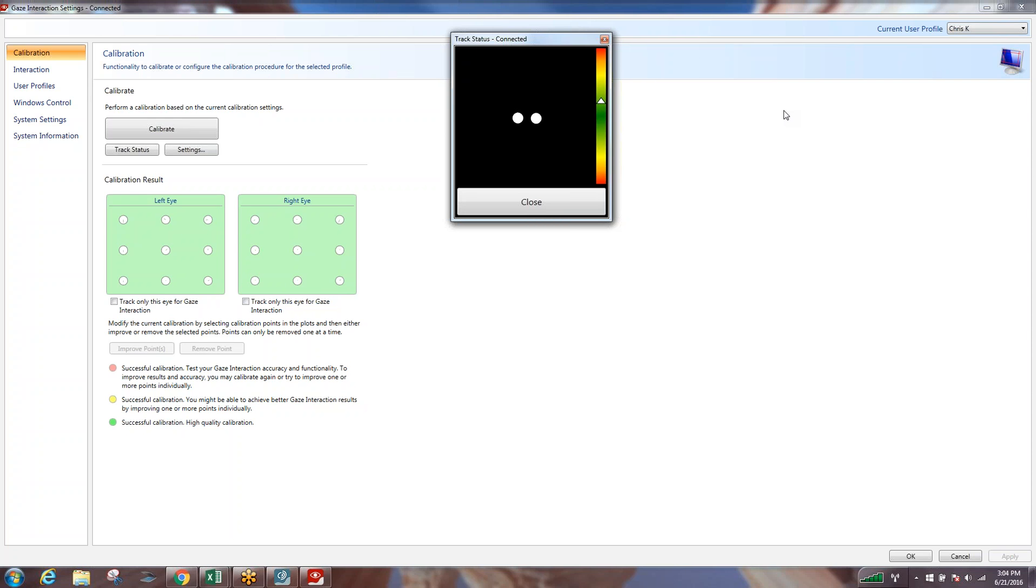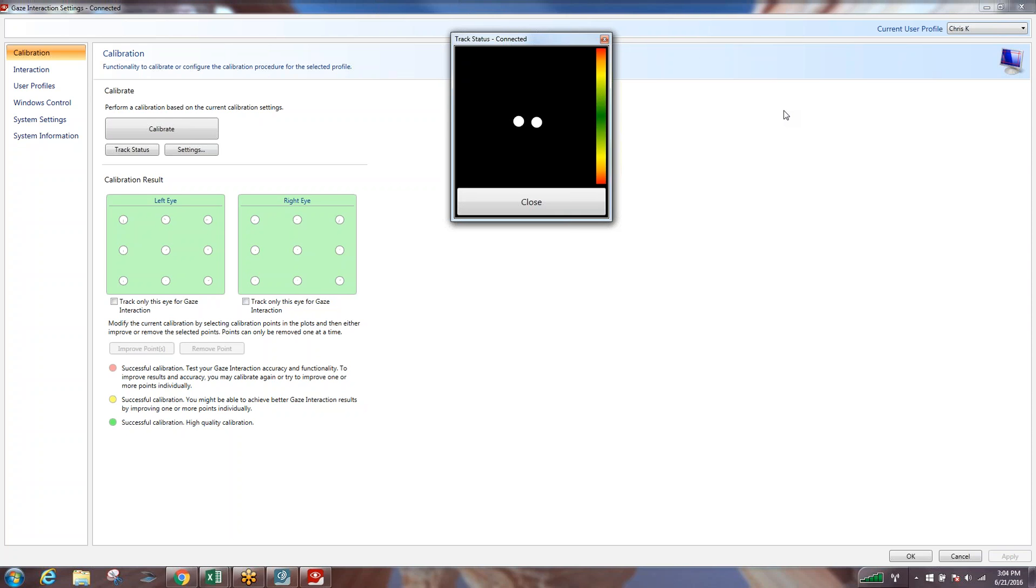If we are getting a fluttering with the eyes, check to make sure if we're wearing glasses that the glasses are clean. Make sure there's nothing highly reflective behind us like a window or a mirror, and make sure that we don't have another direct light that would be bouncing off of our eyes or off of our glasses that might cause interference with the illuminators coming from the speech unit itself.